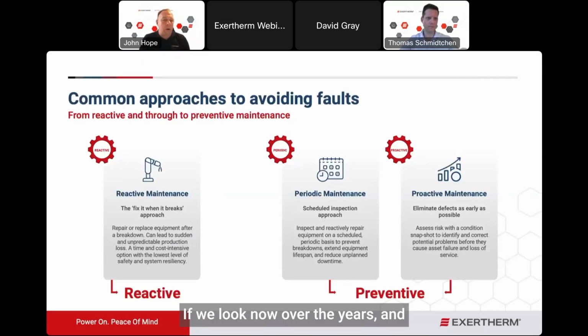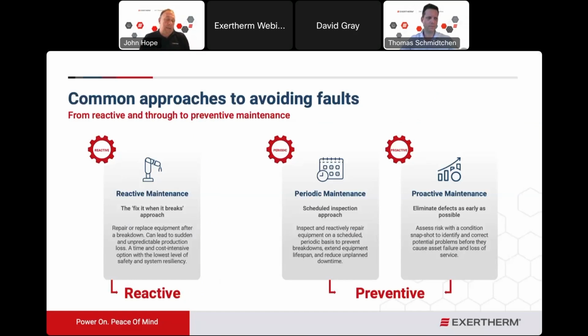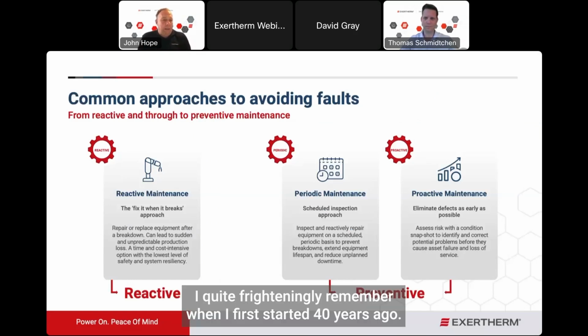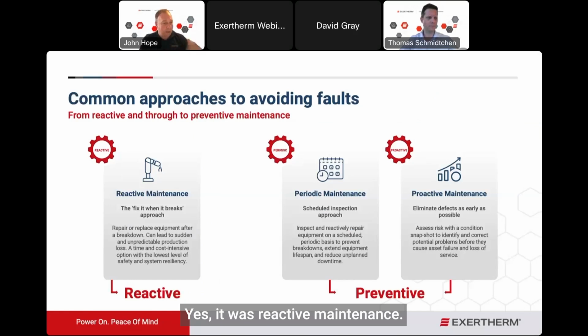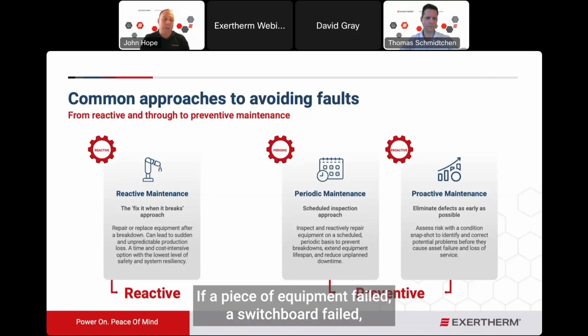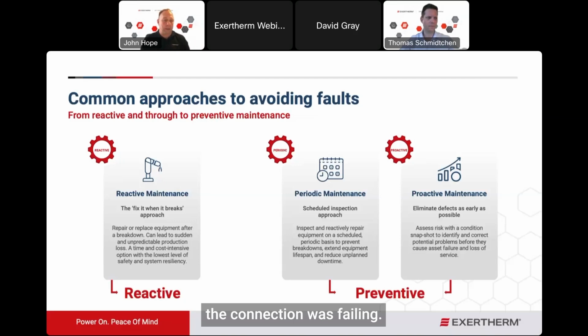If we look now over the years, and I quite frighteningly remember when I first started 40 years ago, yes, it was reactive maintenance. It's where it all started. Everybody reacted to a problem. If a piece of equipment failed, a switchboard failed, a connection was failing, you reacted, but it was too late. Generally, you were too late. You were having to fix it as it was broken.